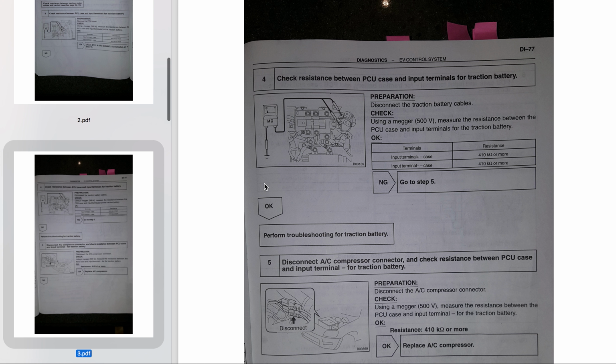Then it has you check the resistance at the battery input leads, which is on the right side of the PCU case. In my case, it was still less than 100 kiloohms, so that means it was no good. Then you disconnect the battery input cables. Now you've taken the battery pack out of the system, and you've taken the motor out of the system, and you're checking the insulation resistance for everything that's in the power control unit, the suitcase as they call it, and a few places where it comes out of the power control unit for the air conditioning and the heated windshield cabling as well. When I tested this, it was still no good.